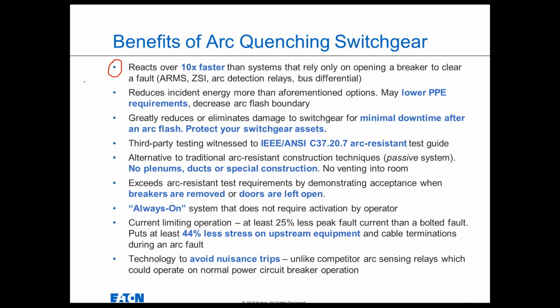But that's sort of the idea behind the test. With our arc quenching switchgear, if you have a door open, those cotton indicators will still not burn. And that's pretty much unheard of. I mean, this really represents a quantum leap above traditional arc resistant equipment, which, as Chris explained, needs to be completely buttoned up in order to be able to contain that massive amount of energy that's released when there's an arc flash event. Our arc quenching switchgear is also an always-on system.